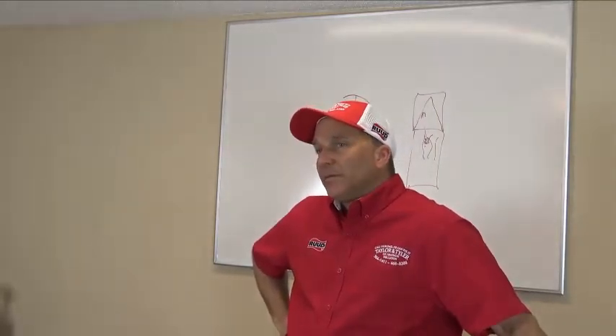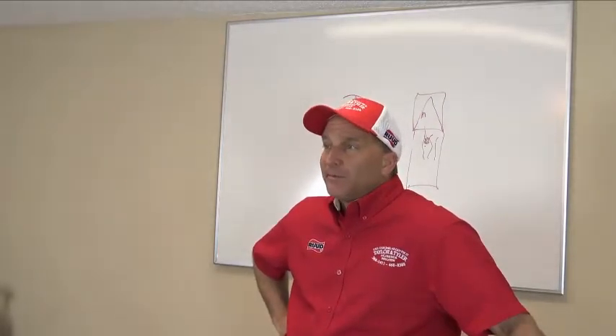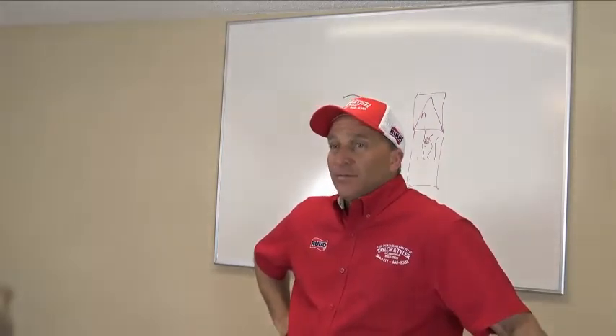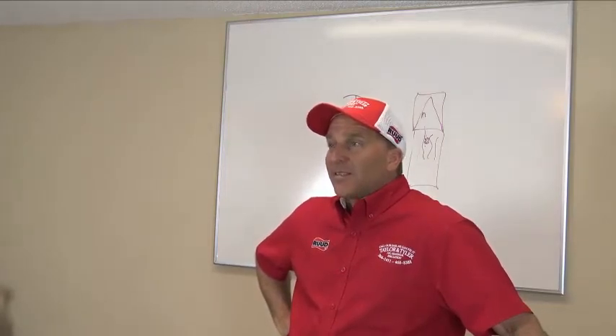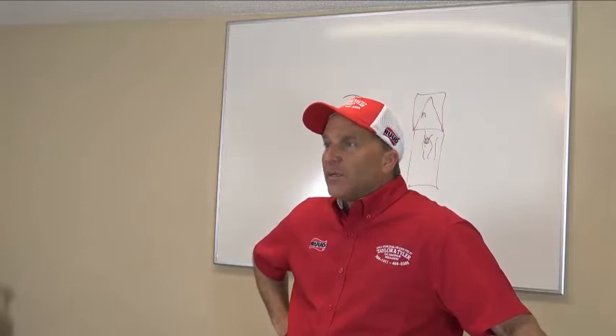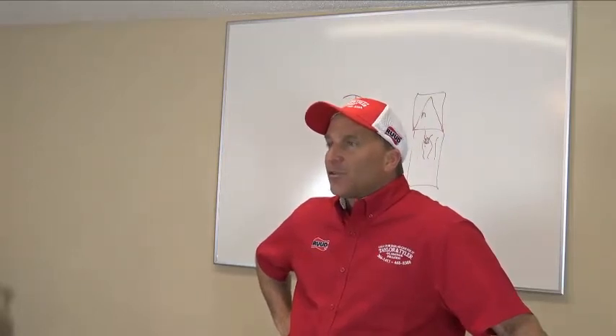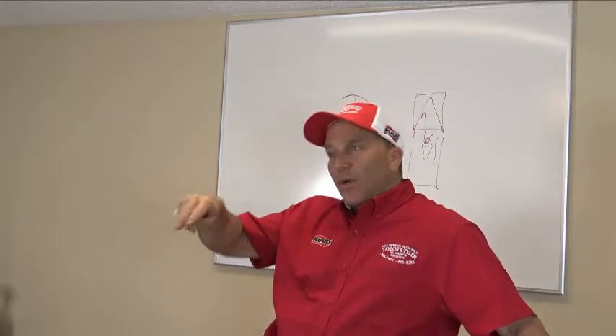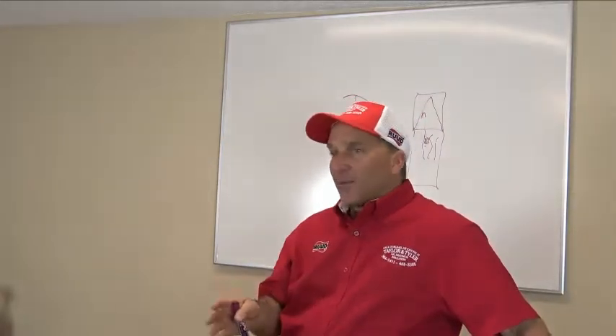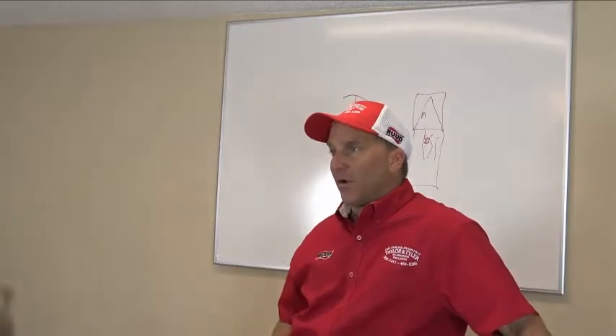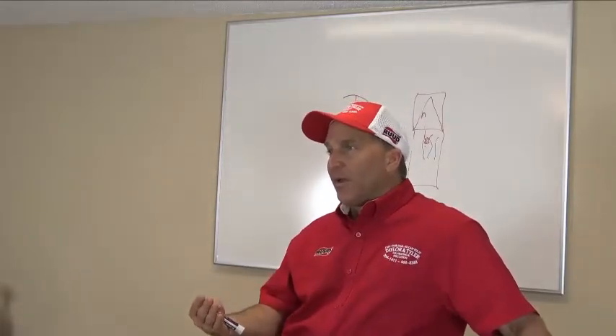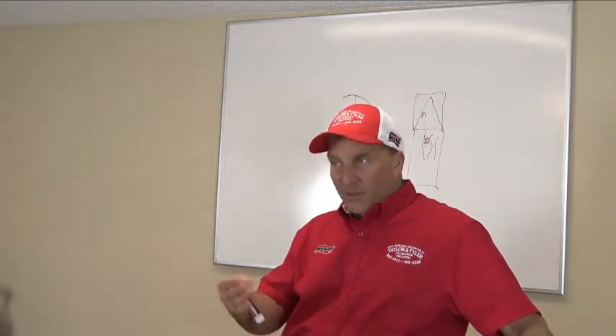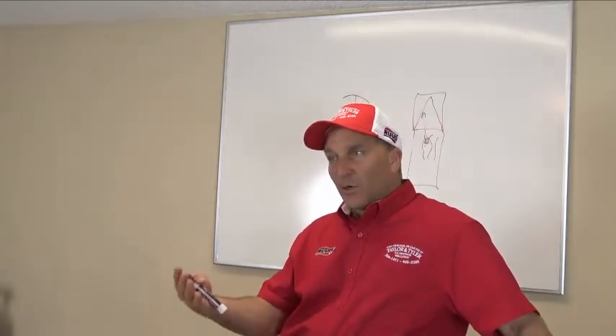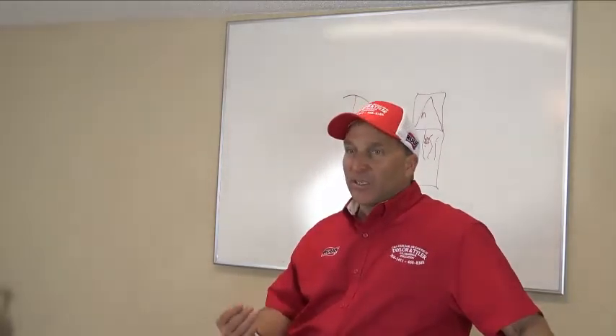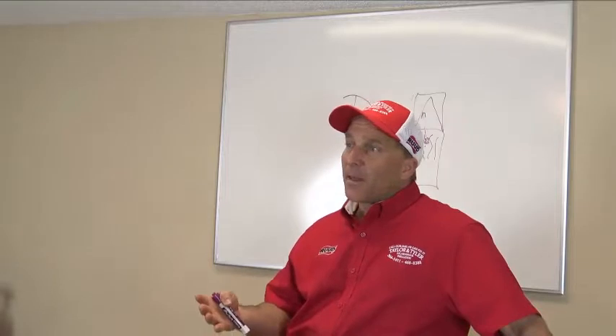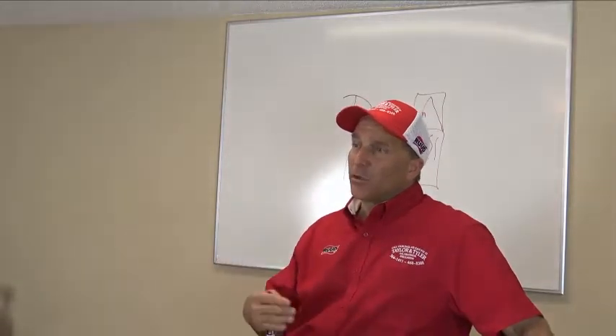You know what it could mean? Whoever charged the system up went beer can cold. That's no joke. Okay? So, and the sight glass cleared at 4 degrees. Okay? But it's still not charged properly because the condenser tells you what head pressure to bring it to. That particular condenser may be a 6, 8, 10, 12 degree subcooling on it, okay? So if you know what it's supposed to be, and you're reading 4, and it's supposed to be 10, then go to the customer and say, you're a little bit low on refrigerant. But I'm going to tell you, I know your system's been cooling fine, everything else looks good, but you're 6 degrees low on your subcooling.